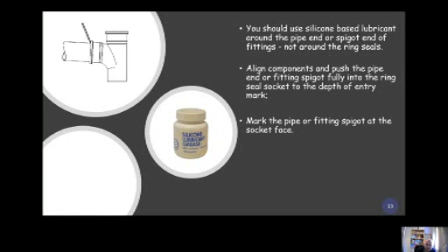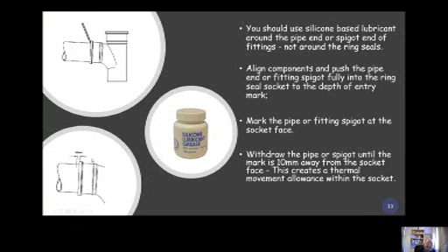And this is one that Guilds like to ask about. According to City and Guilds, whenever we make a push fit joint, we should always pull the pipe out 10mm. So we'd make a mark on the edge at the depth of the slip, like you can see up here, and then we'd pull that out 10mm. That would allow for a space for thermal expansion.